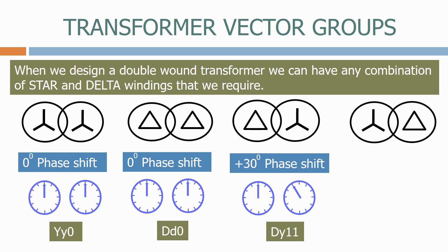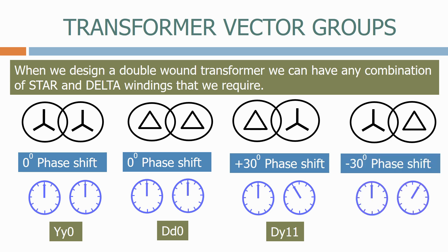Let's now look at a star-delta transformer. Again, because of the physical arrangement, a star-delta transformer also has a 30-degrees phase shift, but in the other direction. The clock faces represent this, with the secondary winding now showing 1 o'clock. It's classed as a Yd1 transformer.